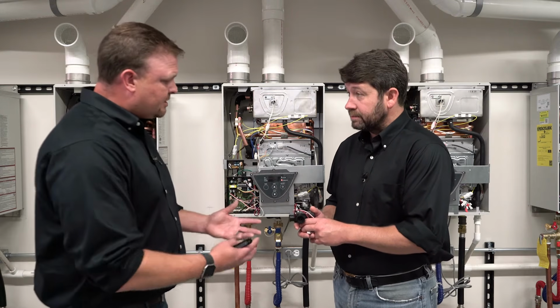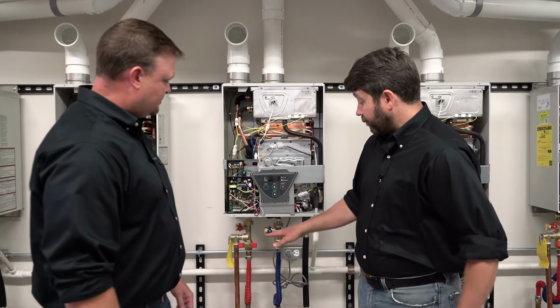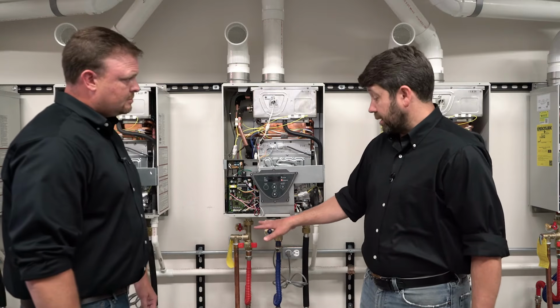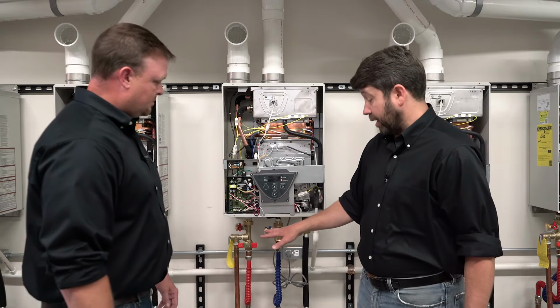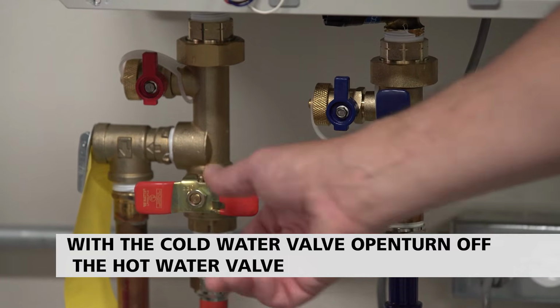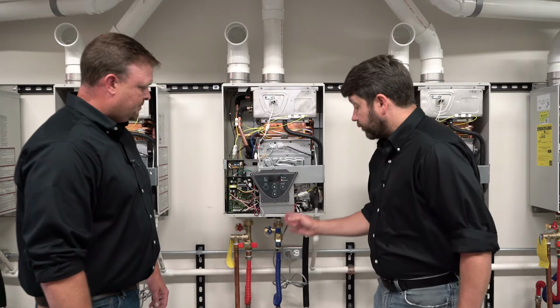So how can we check that? So what we want to do is first, of course, make sure that hot and cold are connected correctly, or at least we think they're connected correctly. Now, with the cold water valve open on the isolation kit, we're just going to turn off the hot water valve. Okay. And that way we know cold water is coming into the heater.